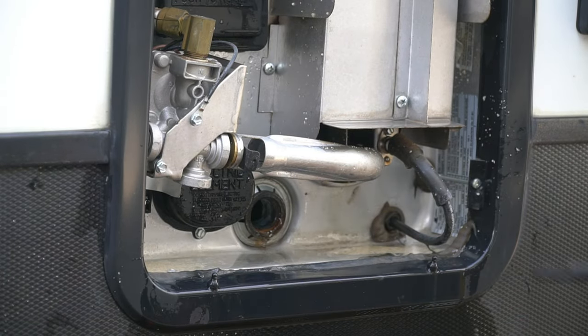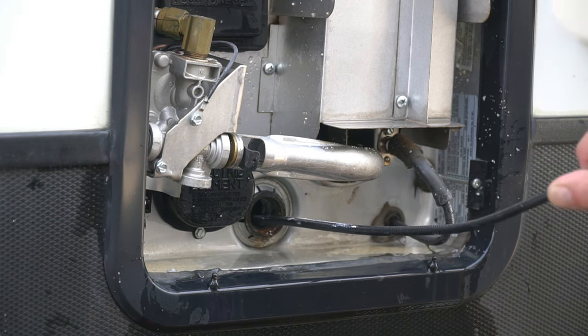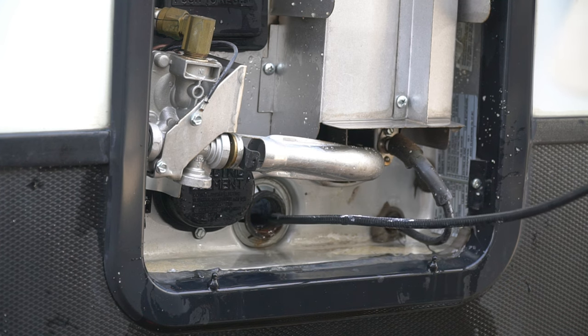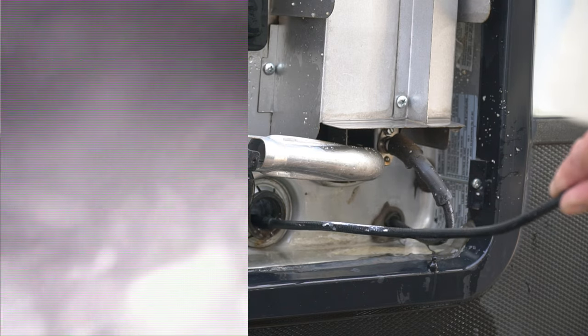I'm also going to try turning on our city water connection to use that water to help rinse this out as well. Let's go in for another look. There's still lots of material, but it's mostly at the opening, which means we're getting there. If I go back further, it's getting nice and clean in there. That's where this boroscope comes in handy — I can actually get in there and see what's left to do.